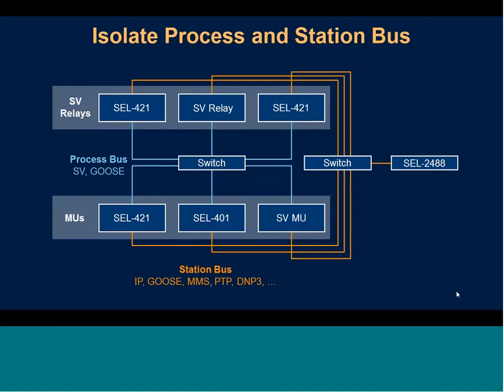So just a very simplified architecture of that. We generally are going to have two Ethernet networks. The main one that's new is this process bus in the middle, and what this does is connect the merging units in the yard. So on the bottom, we have all of our merging units connected to all of our relays, which generally would be inside a centralized control house.